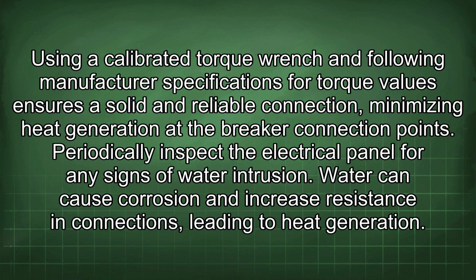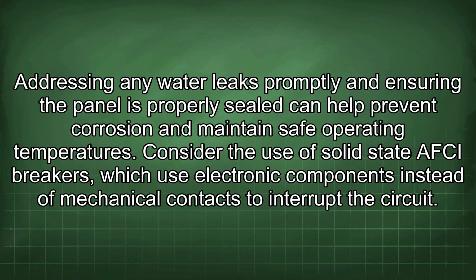Periodically inspect the electrical panel for any signs of water intrusion. Water can cause corrosion and increase resistance in connections, leading to heat generation. Addressing any water leaks promptly and ensuring the panel is properly sealed can help prevent corrosion and maintain safe operating temperatures.